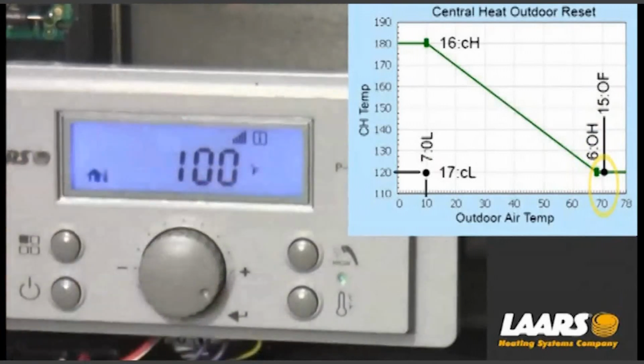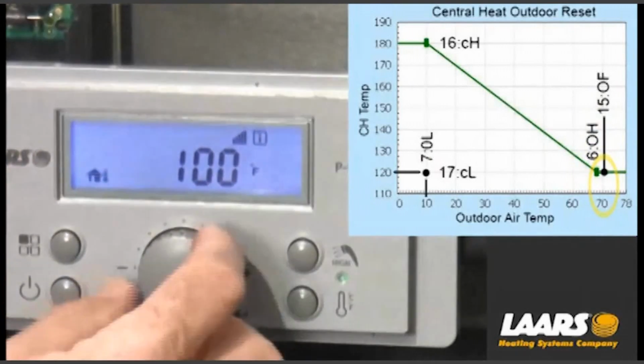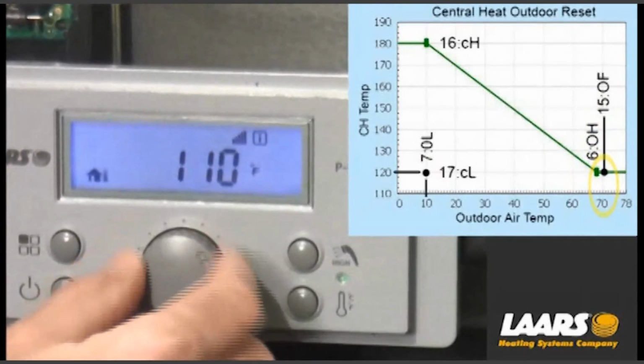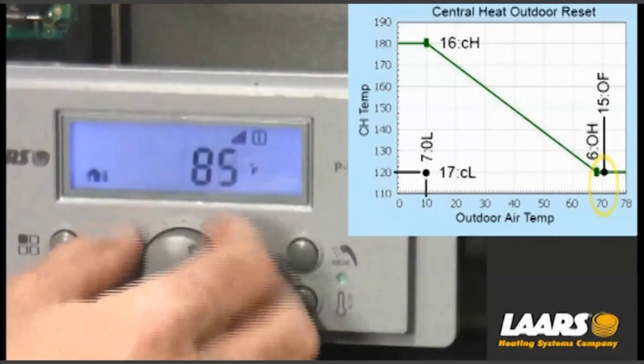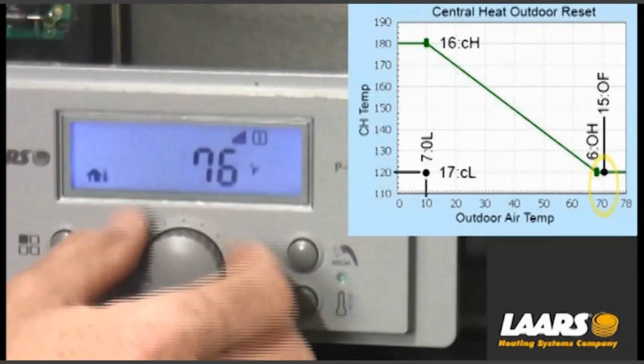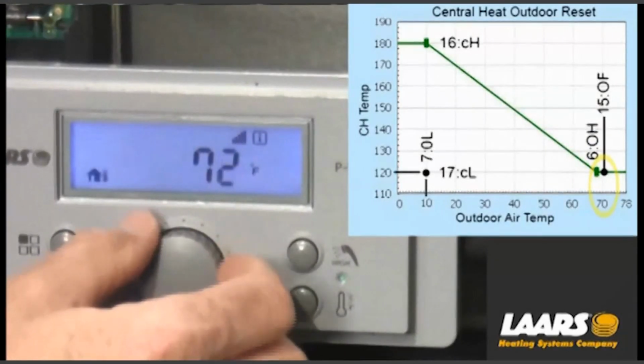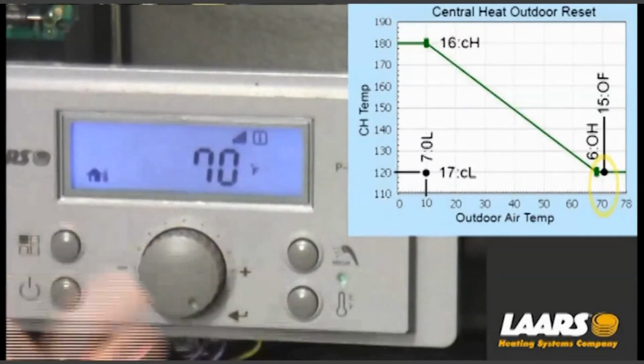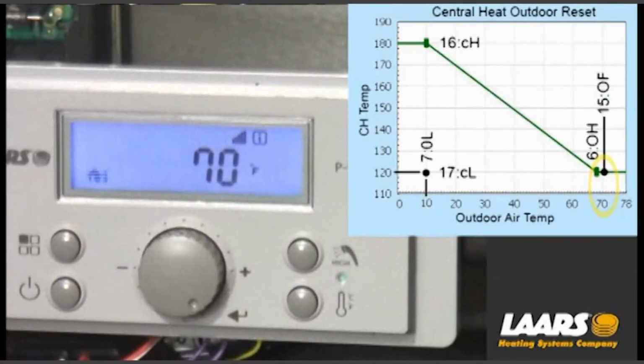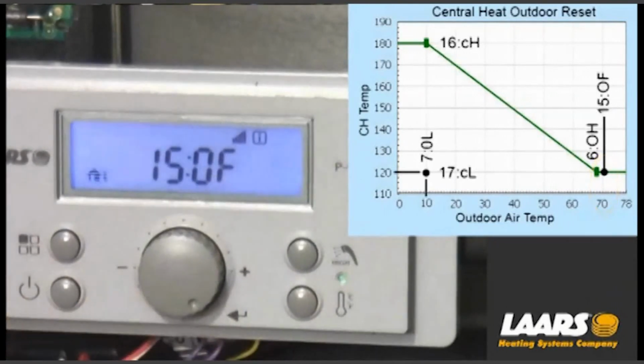Press select, it's defaulted for 100 degrees. In this example, I'm going to turn it down to 70 degrees of outdoor air. So at 70 degrees of outdoor air, if somebody turns on a thermostat, the heat will not come on. I've adjusted it down to 70, press select, and now it'll store it.